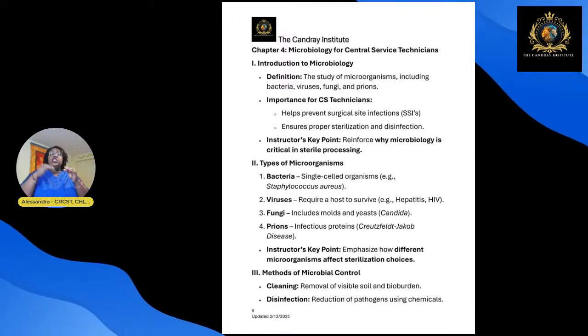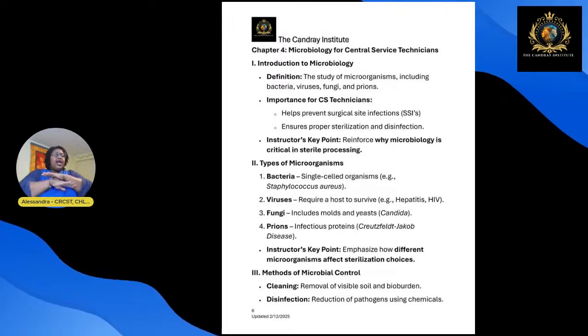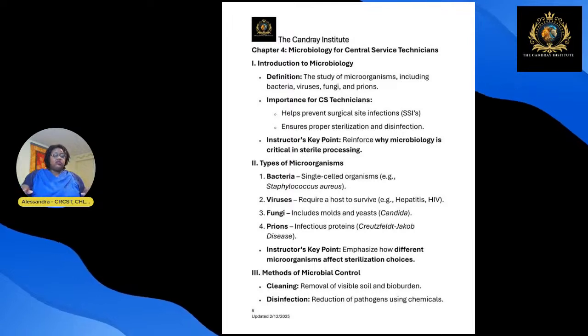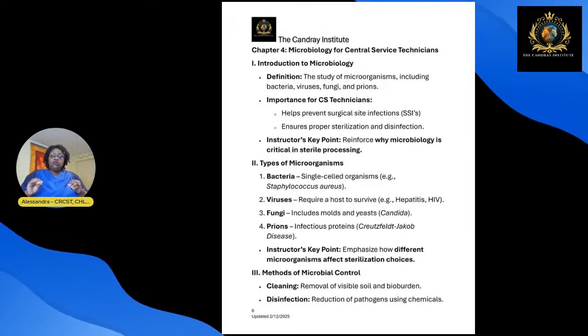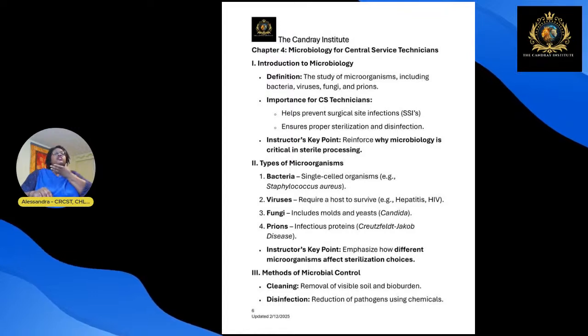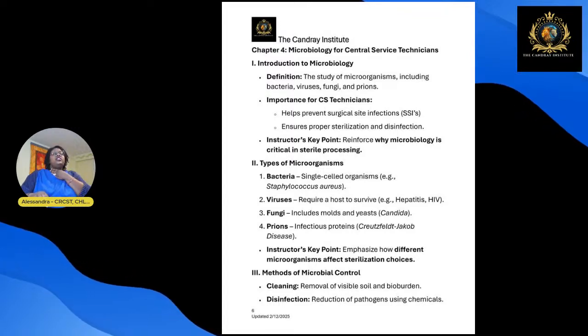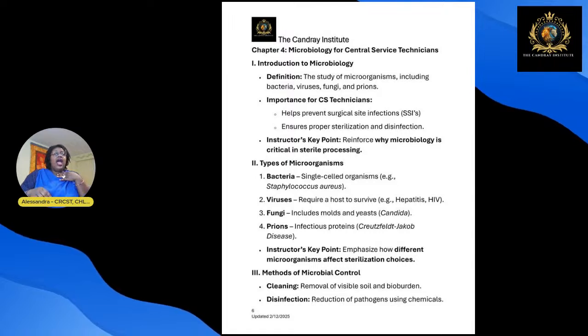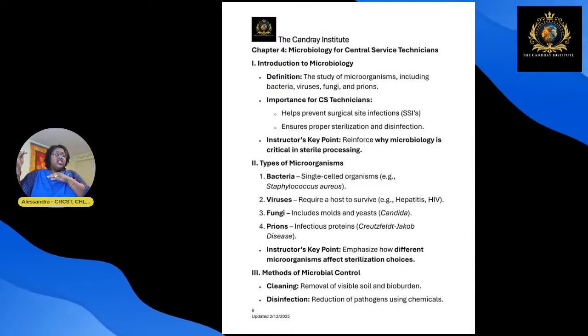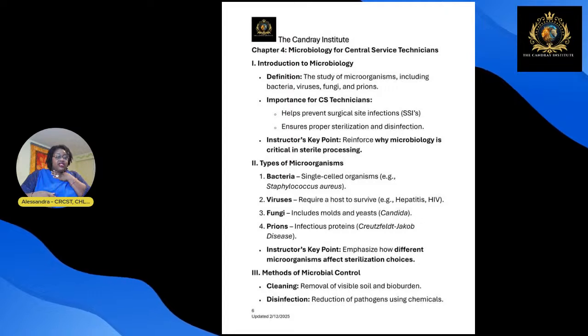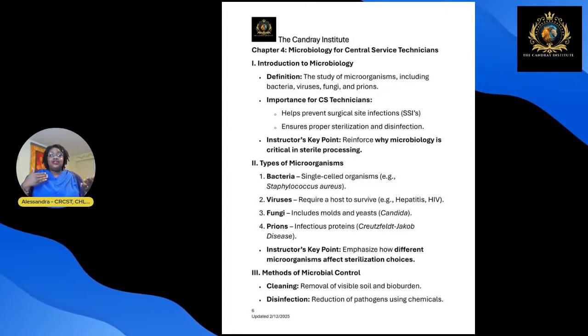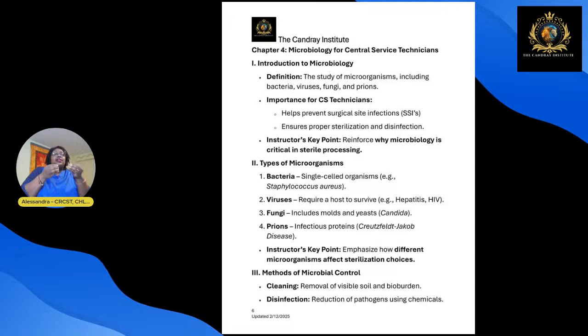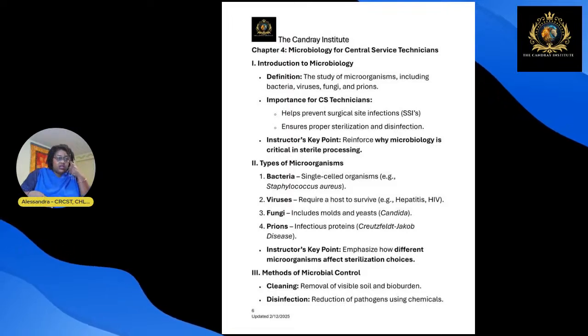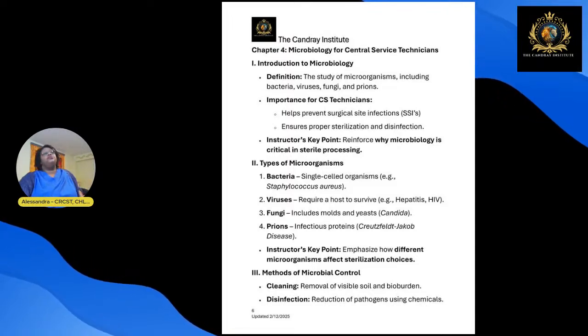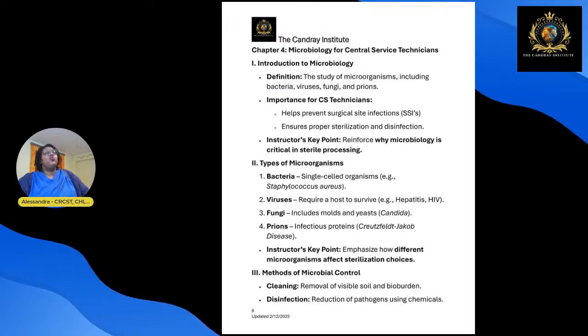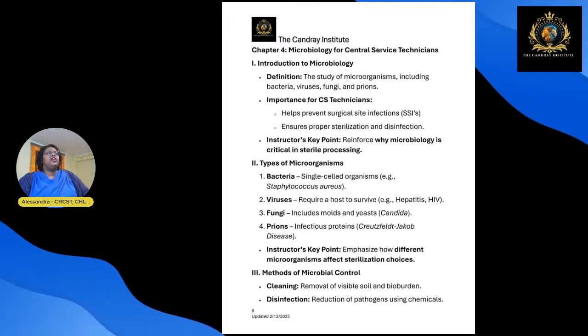Because remember, until we get to terminal sterilization, we're not getting rid of all the germs. We're getting rid of most of them, but not all of them. If I'm doing a procedure on something that the Spalding classification considers dirty, like a throat, I might not have to go to the highest level of sterilization for that instrument because this cavity is considered dirty. Same thing with the anus. It's considered dirty. So I might not have to get it as clean as if I wanted to do eye surgery or cardiac surgery. The Spalding classification helps you with that. Any questions so far?